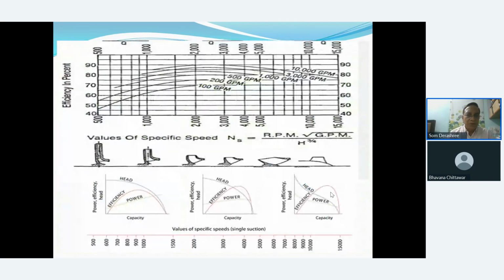This is another way of showing the same thing. This is the specific speed, from 500 to 15,000 on the x-axis. This is the efficiency in percentage, and this is the flow. You see at 10,000 GPM, this gives you a good amount of efficiency, almost about 90% in this specific speed range. And these are the corresponding curves, from mixed flow to axial flow, radial to axial. The curve moves from vertical, gradually to horizontal, and in axial it is absolutely horizontal. If you see the curves on this side, radial, these are the typical efficiency curves.